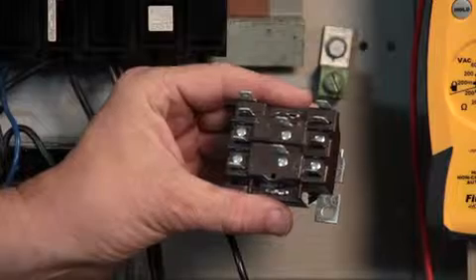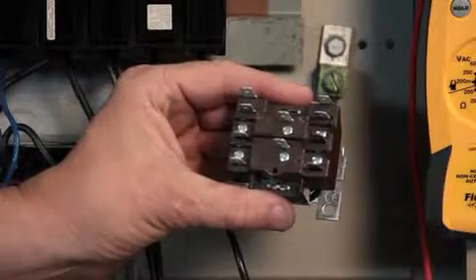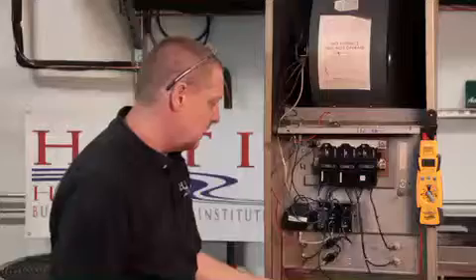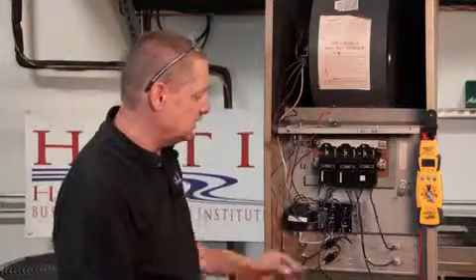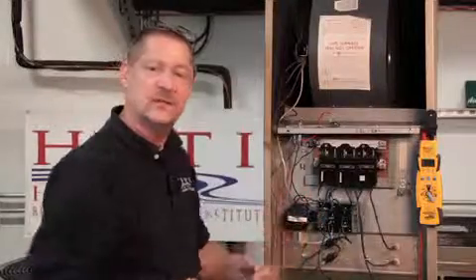When they open, we should see that open back up. So I'm making sure that the contacts both close and open, making sure it's not stuck. And we'll check our sequencer to make sure that it is stepping everything on and stepping everything back off.